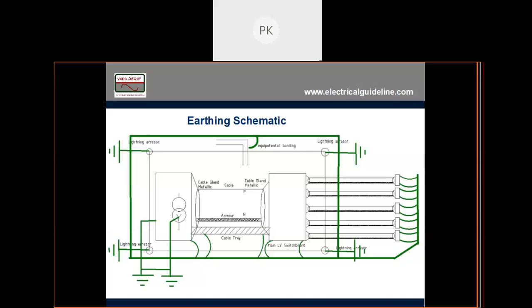For example, your steel plant or oil and gas industry or continuous process industry, they don't want the motor to get burnt out during a fault. They will earth the neutral of the transformer through a resistor. So I will be taking that topic next month. After that, I will take earthing of generator, power plant generator. After that, I will be coming to solar PV.